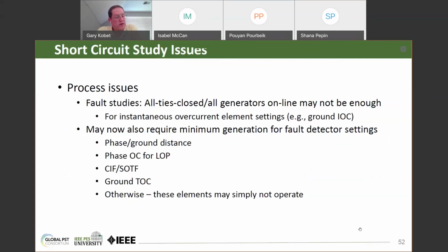The next slide talks about short circuit study issues. Typically, what protection engineers will study is all ties closed, or all system intact, all generators online, for setting instantaneous elements, for example, ground instantaneous elements. But now the case may be that we also need to study minimum generation to make sure that the fault detector settings are exceeded, or overcurrent elements have enough quantity to make operational decisions, trip decisions, directional decisions, those kinds of things. Otherwise, the elements may simply not operate.